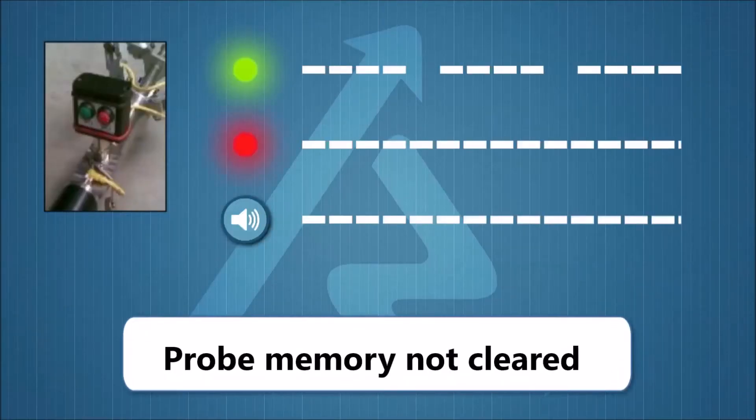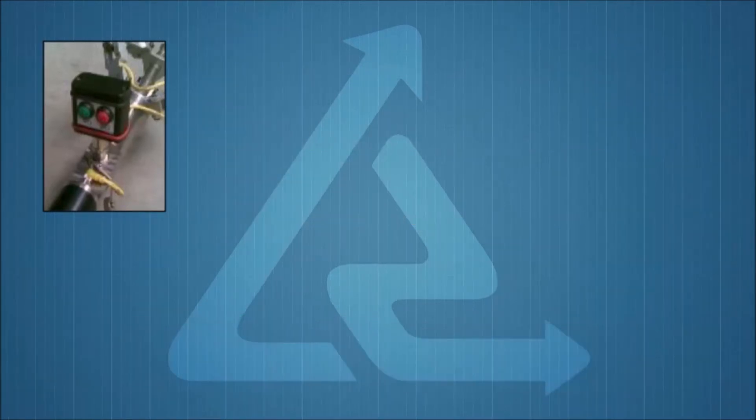If, however, you hear continuous beeps, the green LED flashes four times intermittently, and the red LED flashes continuously, the memory of the probe must be cleared first. Consult the extraction manual for the clear memory procedure.